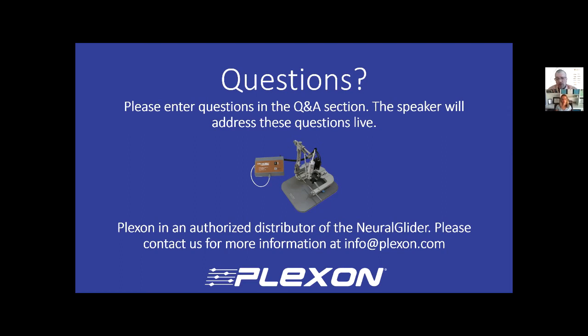Another thing I noticed, just playing around with the Qualia probes with vibrating: there was one that was the longer length probe, a 5 millimeter, and it seemed to have a lot of out of plane at the higher powers. You could add a little drop of fluid onto the end, and that seemed to channel all the vibration in the axial direction, or at least restrict the out of plane movement. Probably just the extra mass of the fluid on the tip tended to knock that down. So even when you observe a little bit of out of plane vibration, there's not much force or momentum behind it. I think that's it. Okay.